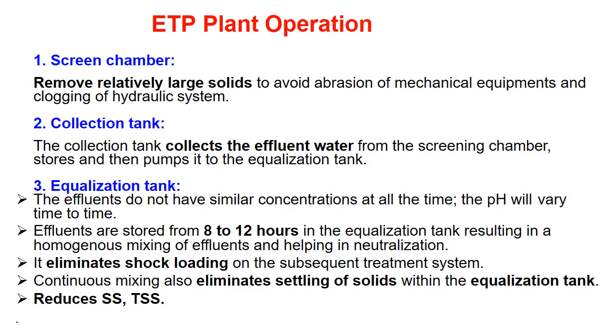Now we will discuss ETP plant operation. The first is the screen chamber — it removes relatively large solids to avoid abrasion of mechanical equipment and clogging of the hydraulic system. Number two is the collection tank, which collects effluent water from the screening chamber, stores it, and then pumps it to the equalization tank.